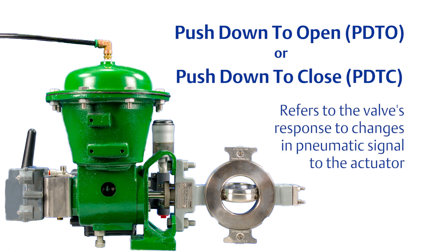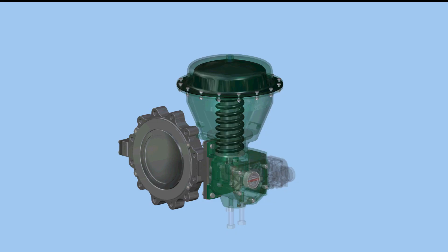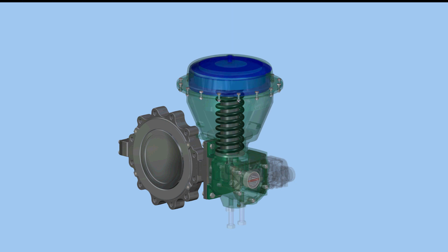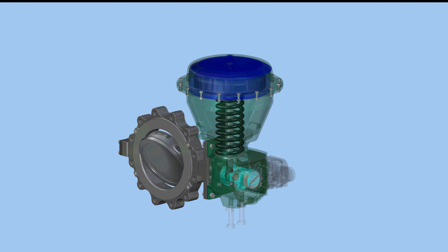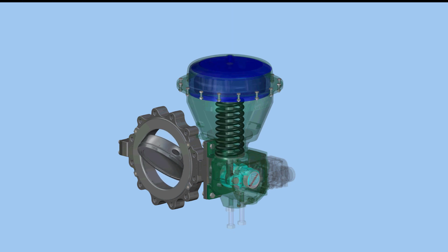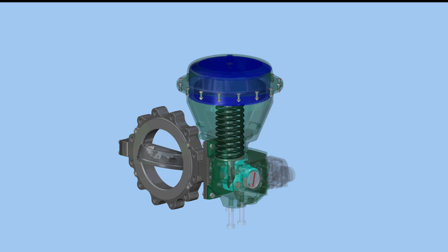This refers to the valve response to changes in the pneumatic signal to the actuator. In this example, a control valve with a spring and diaphragm actuator is configured for push down to open. As increasing pneumatic pressure moves the diaphragm, diaphragm plate, and actuator stem down to rotate the lever, the drive shaft rotates the valve into the open position.